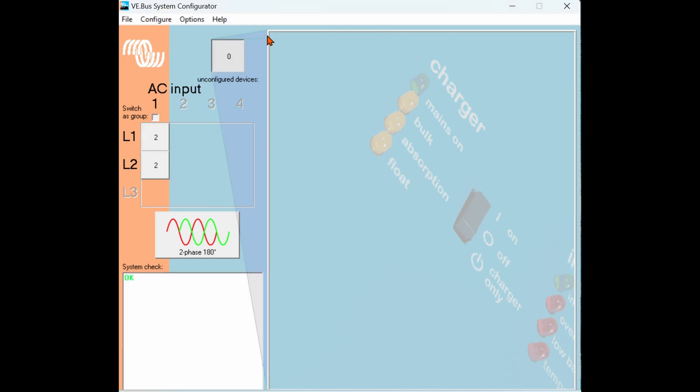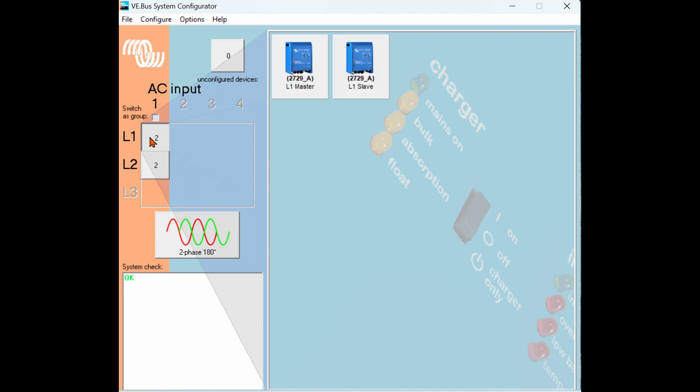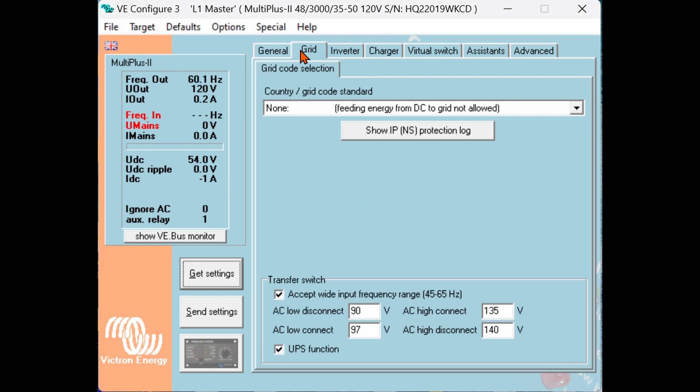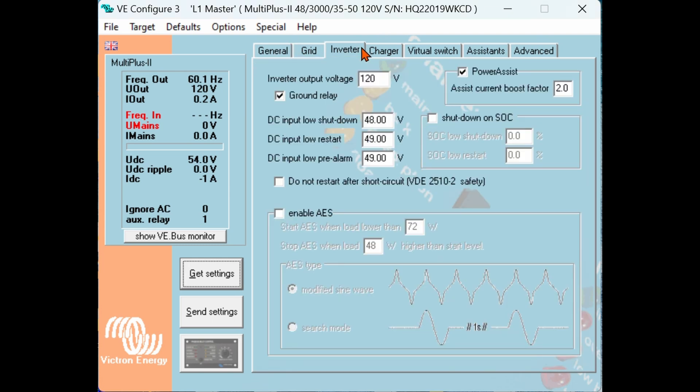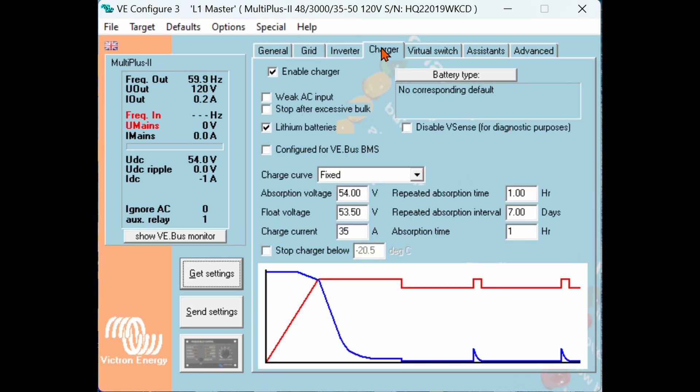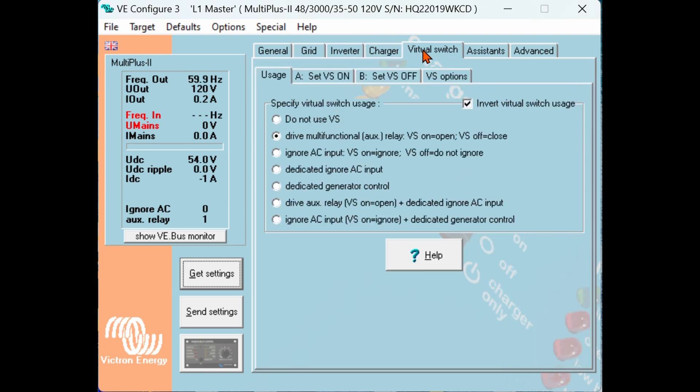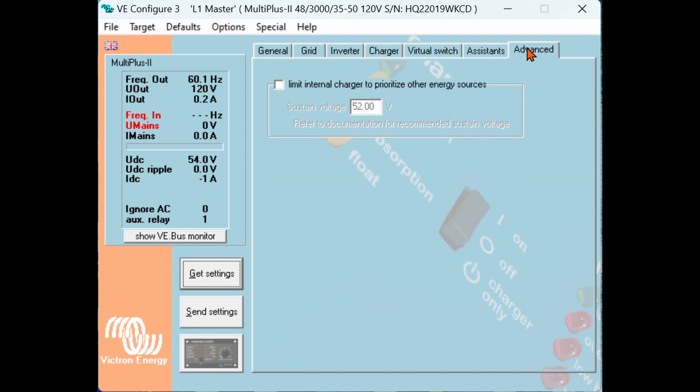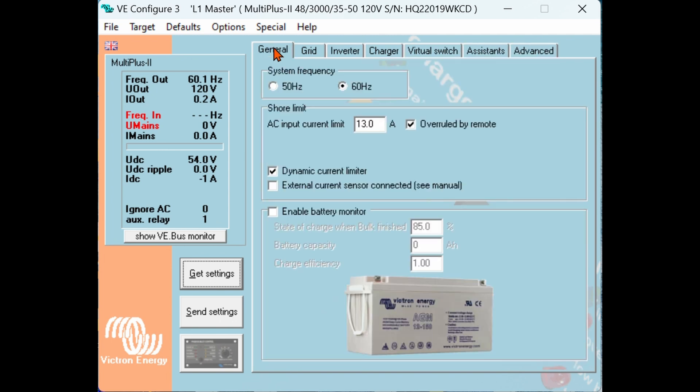So two ways to do this. The first is to right-click on the inverter you'd like to program and choose VE Configure Multi. This will open the VE Configure 3 software to allow inverter specific programming such as battery type, virtual switch, AC input control, low voltage disconnect, etc.